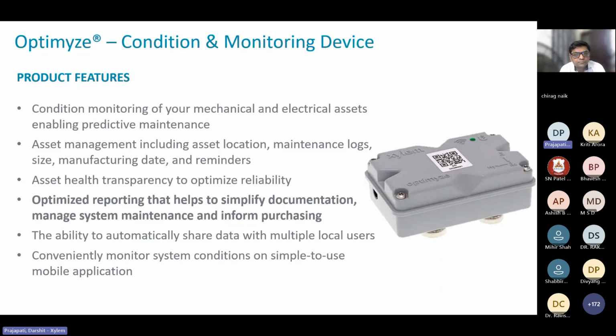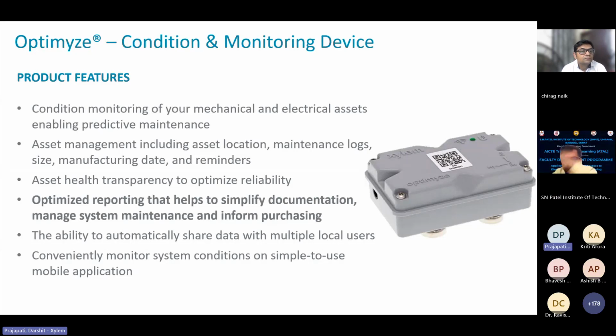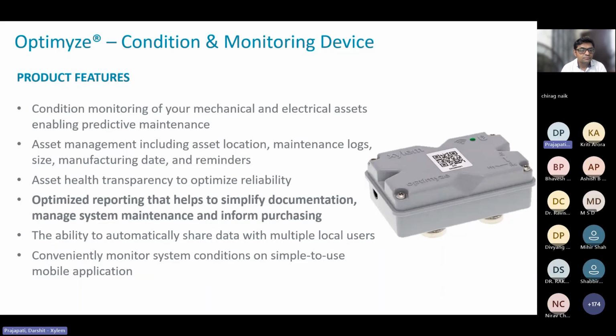This simplifies reporting, helps simplify documentation, manage system maintenance, and inform purchasing. So if any component needs to be procured in advance because of high vibrations, it can predict that, since the algorithms implement machine learning. It can predict whether vibrations are because of bearing failure, cavity in the impeller, or misalignment between the motor and pump. All the signatures of the vibration data help analyze this in a better way.